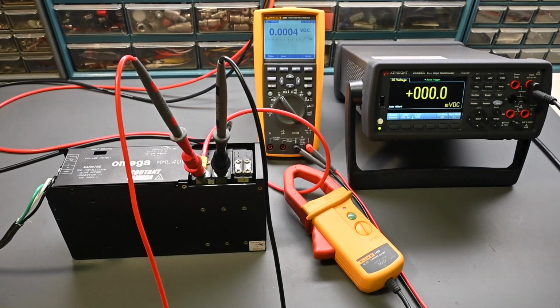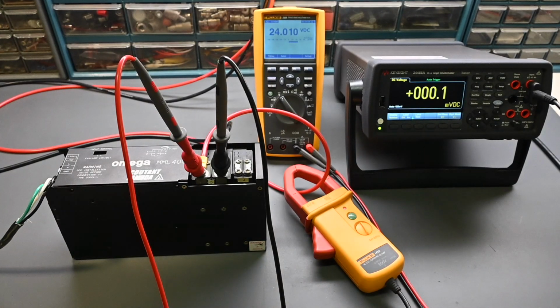All right, and the fan that you hear running right now is up on the dyno load. So you're going to hear the fan kick in on the power supply now when I turn it on. All right, so we have output voltage. That looks very good, 24 volts. So let me switch on the circuit breaker on the dyno load. And I'll start to increase the current. So let's go up to about 5 amps. Right about there. That's pretty close to 5 amps. And voltage is holding up, no problems there.